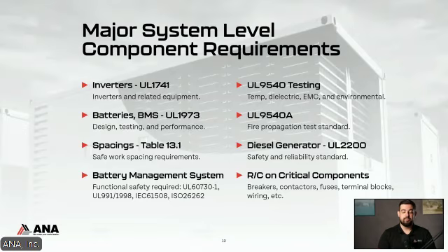Diesel generator. So if you have a chemical or a thermal energy storage system, and those definitions you can find in the standard itself, but those two types of ESSs you must meet UL 2200 if you incorporate a diesel generator into the system. So yeah, I would definitely look out for that if you have a chemical or a thermal ESS.